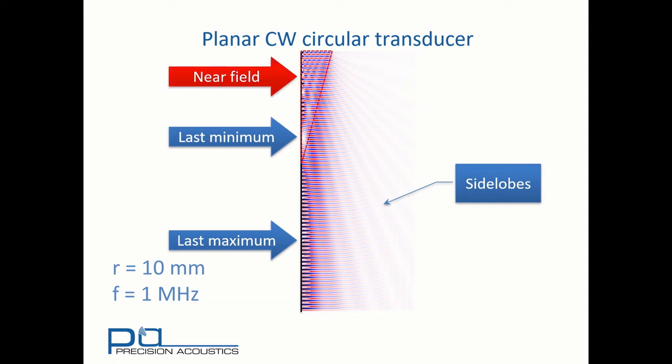Also, if we look at the region shown in red, there's considerable variation of pressure amplitude within this region. This is often described in textbooks as the classical near field of the transducer. But it's important to realise this is only evident when we're driving a transducer with a continuous wave. If we use much shorter signals, there's far less opportunity for interaction of edge and plate wave components, and many of these near field phenomena disappear.